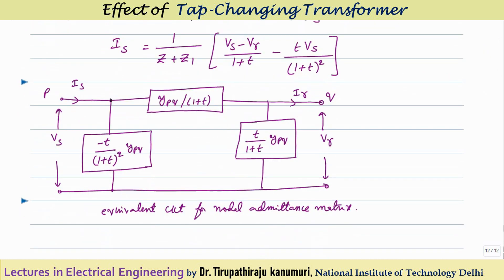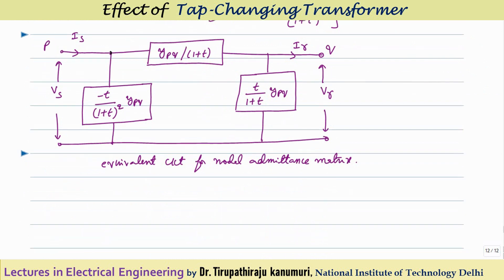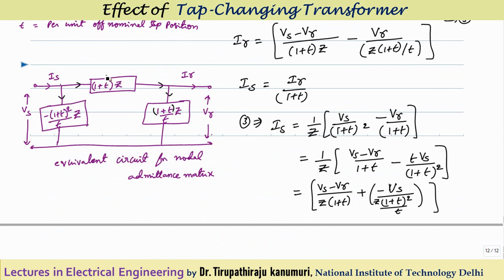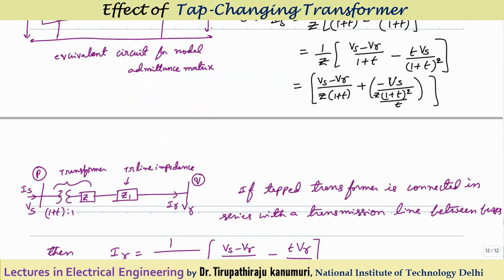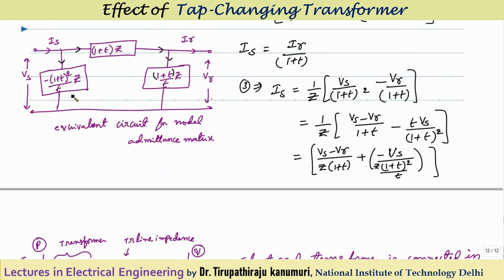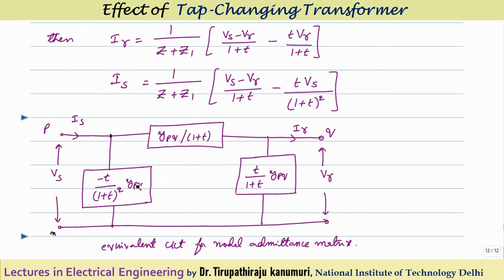Once the equivalent impedance values are obtained, we convert to admittances (admittance = 1/impedance). Taking two nodes P and Q with a reference neutral node, the series admittance is YPQ/(1+T), the shunt admittance at P is −T/(1+T)² × YPQ, and the shunt admittance at Q is T/(1+T) × YPQ.